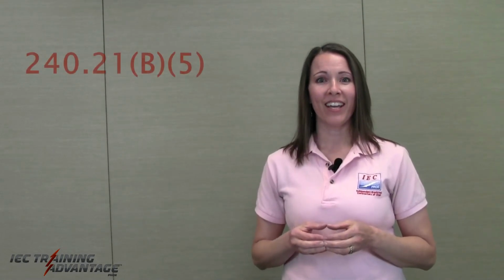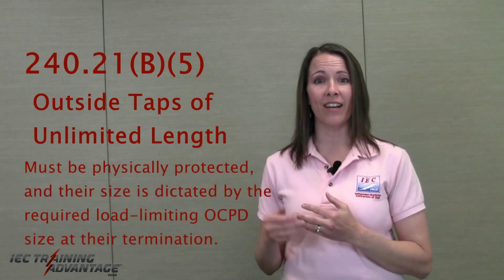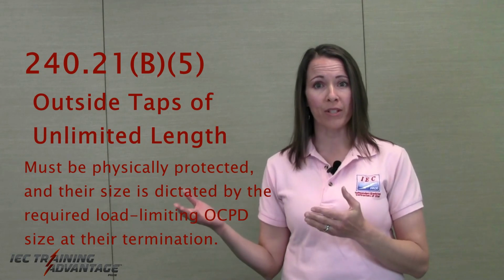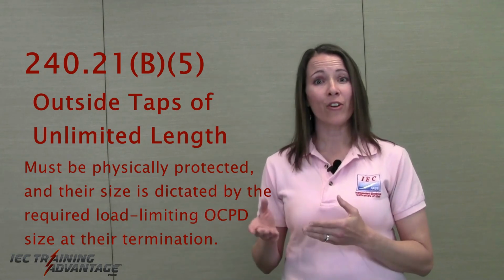And now, finally, 240.21(B)(5), outside taps of unlimited length. These have to be physically protected, like our other taps. They have to terminate in a load-limiting overcurrent protection device. But other than that, there isn't a sizing rule associated with these taps. So there you have it. Branch circuits, feeders, and taps. Branch circuits and feeders don't usually give us too much grief, but those tap conductors with all of their different rules sometimes do. So let's get into some examples.